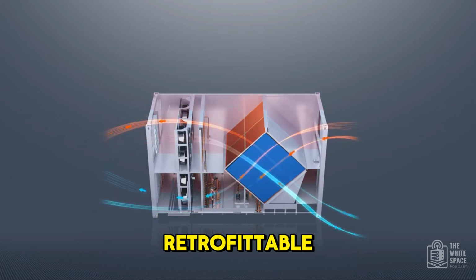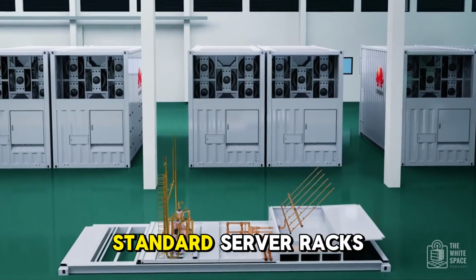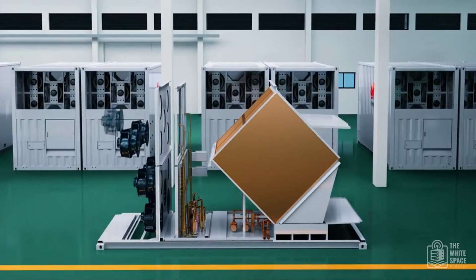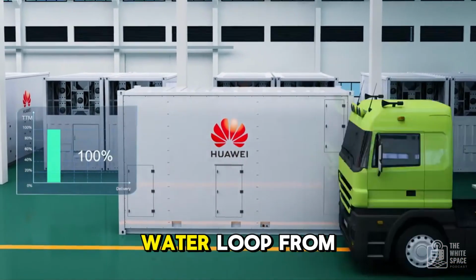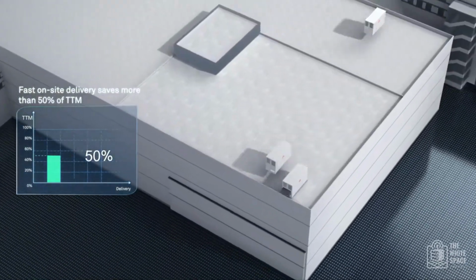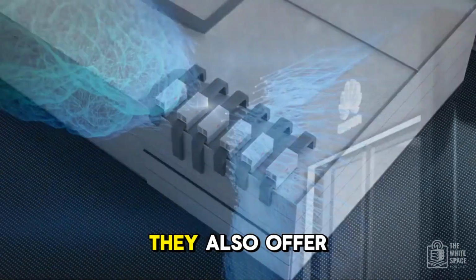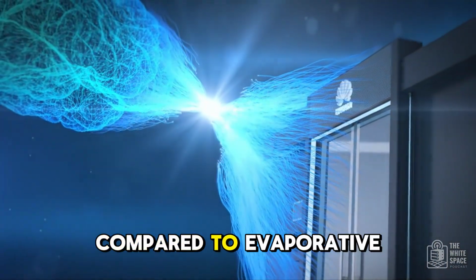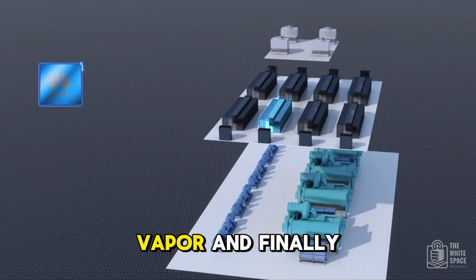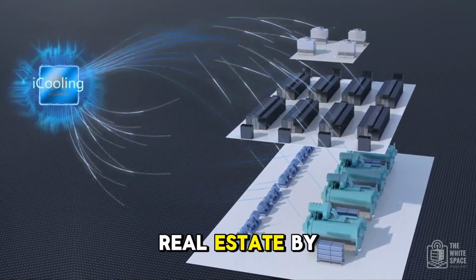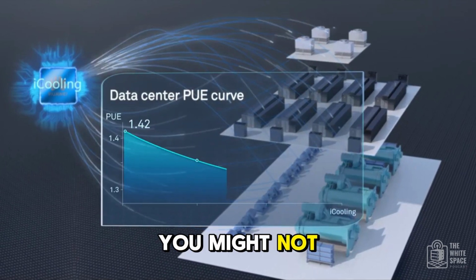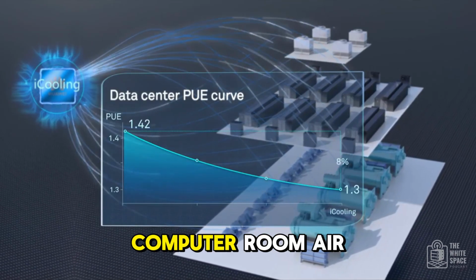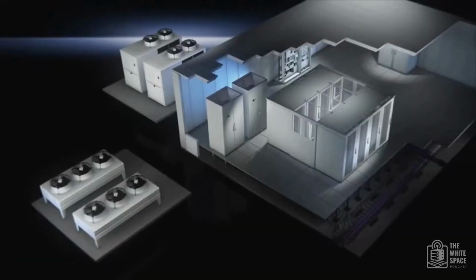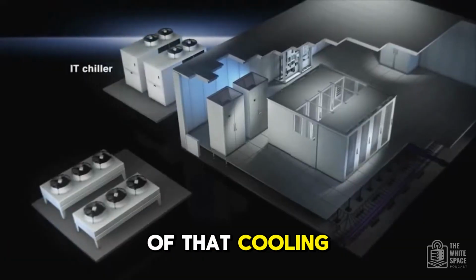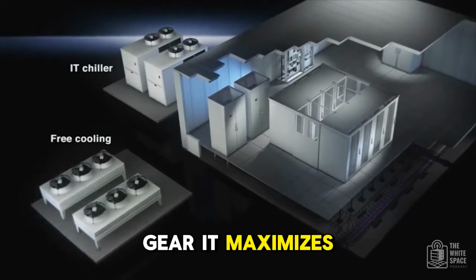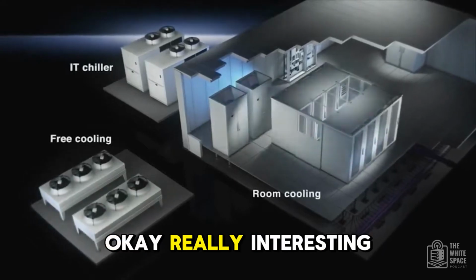They're also very retrofittable. You can often add them onto existing standard server racks, OEM racks, and they can sometimes tie into the return water loop from your existing chilled water system. Being closed-loop liquid systems, they also offer huge water savings compared to evaporative cooling towers that vent water vapor. And finally, real estate. By handling the heat at the rack, you might not need as many large CRAC units, computer room air conditioners, taking up floor space. That can free up maybe 60% of that cooling footprint for more IT gear. It maximizes your white space. Okay, really interesting options there.